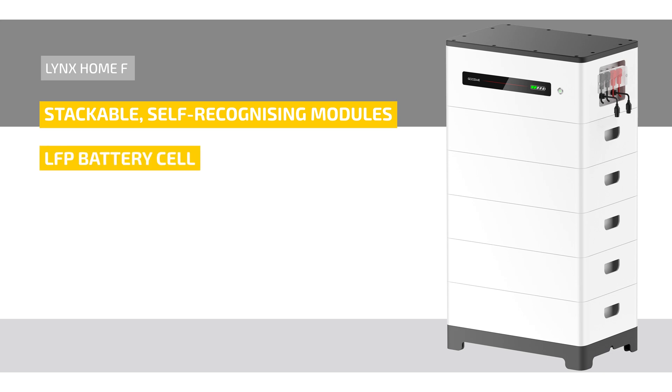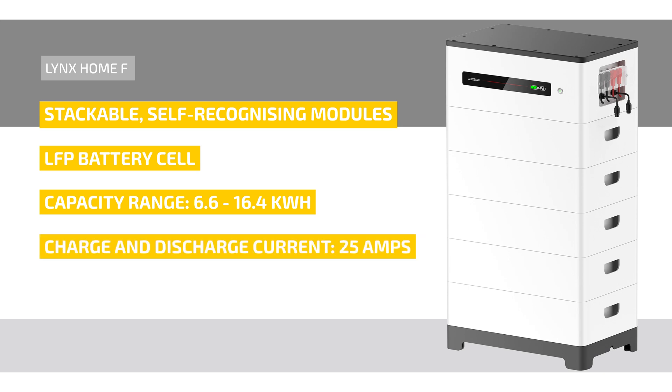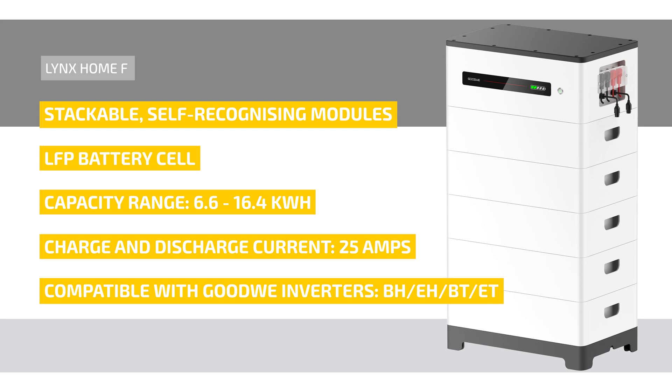Let's move on to the performance data of the Lynx Home F. The Lynx Home F is available with a capacity range of 6.6 kilowatt hours to 16.4 kilowatt hours and has a charge and discharge current of 25 amps. It is compatible with the GoodWe inverter series BH, EH, BT, and ET. The dimensions are 600 millimeters in width, 380 millimeters in depth, and the height depends on the number of modules installed.